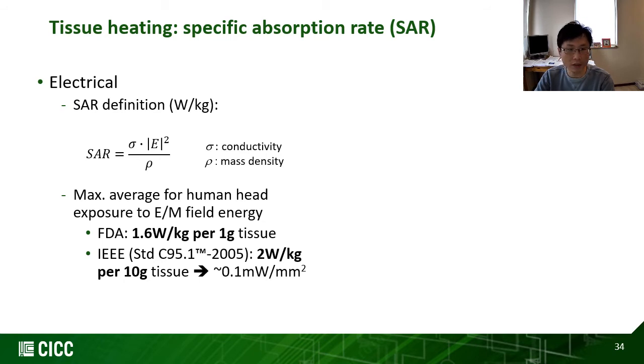For electrical SAR requirements, here is the definition. Sigma is the conductivity, E is the electrical field, and rho is the mass density. The FDA specifies that the maximum average for human head exposure to electrical and magnetic field energy should be less than 1.6 watt per kilogram per 1 gram of tissue. IEEE specifies 2 watt per kilogram measured every 10 gram of tissue. We can translate this, per square millimeter, to around 0.1 milliwatts.